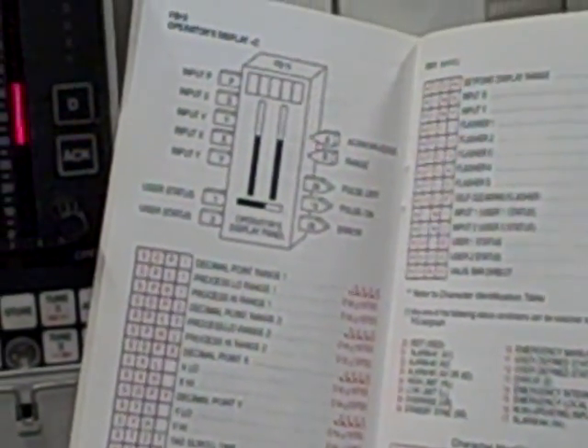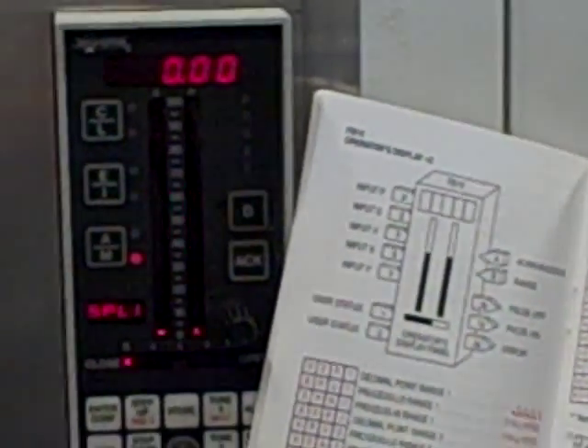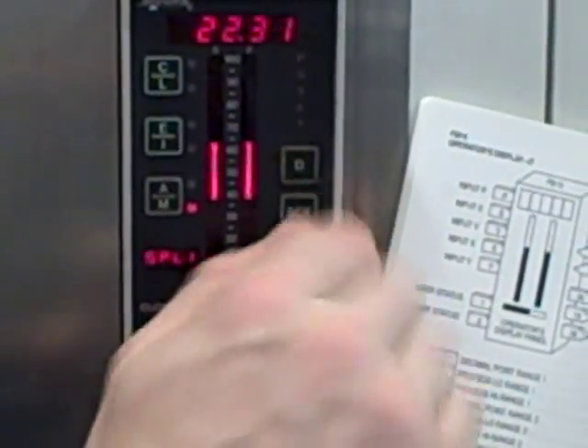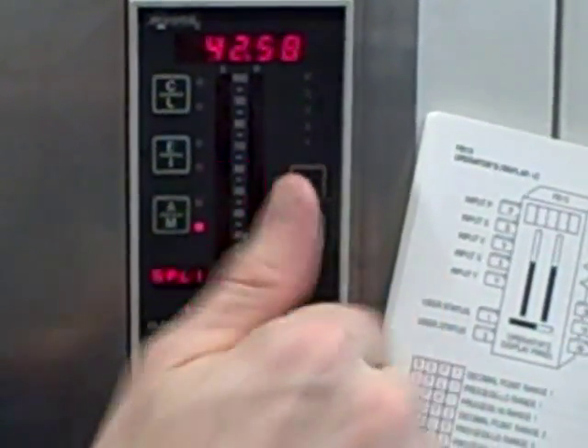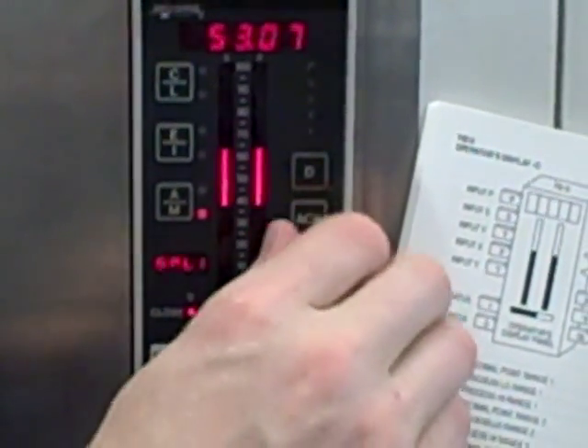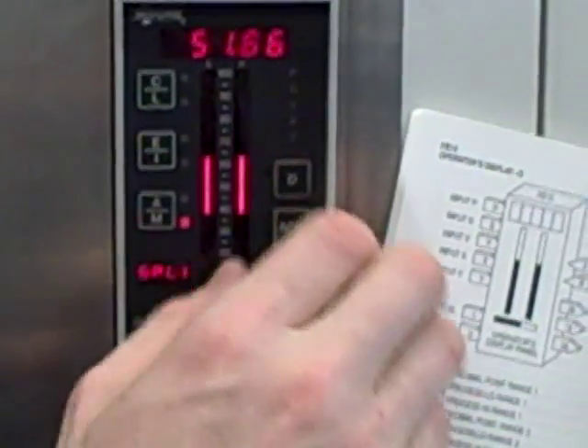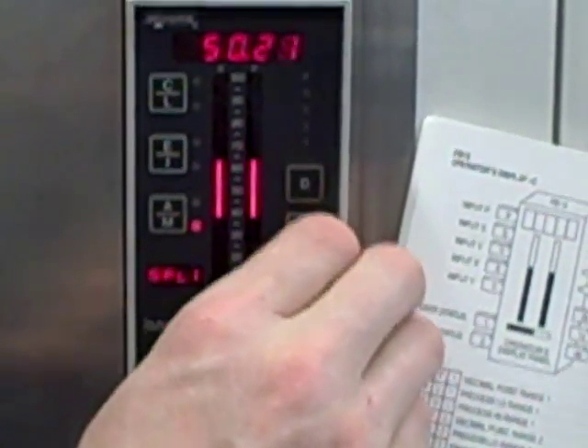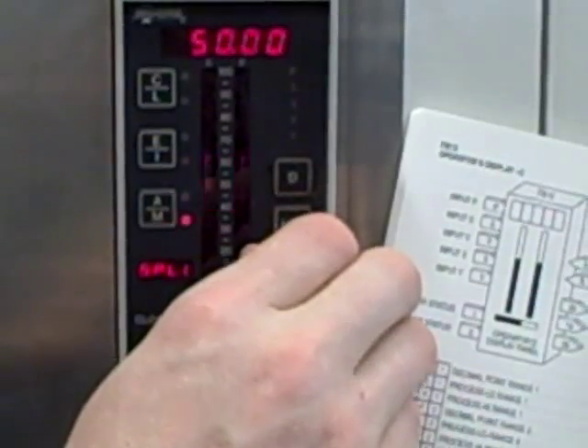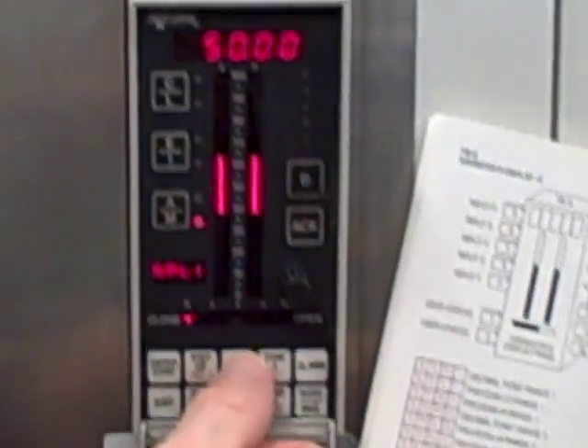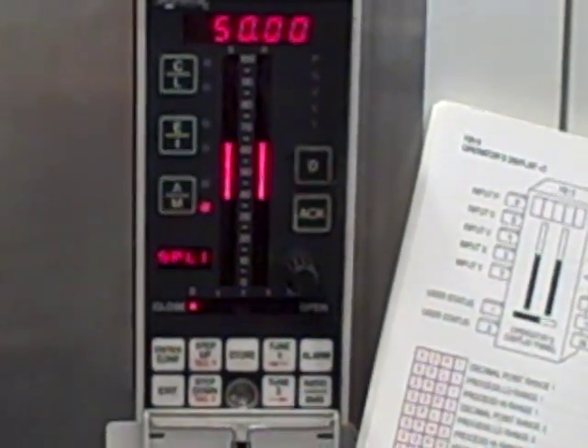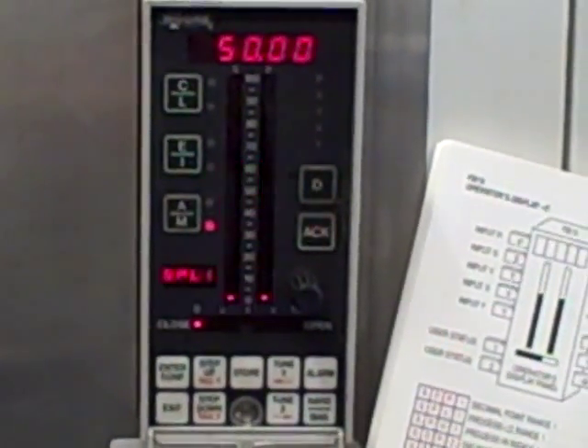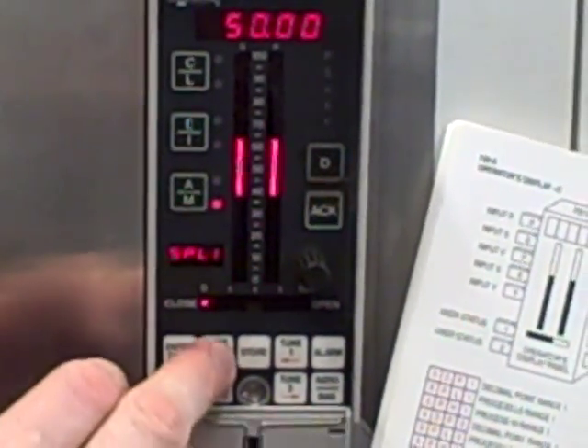The factory defaults for low and high range are 0 and 100 respectively. I don't know where your calibrated transmitter to right now. 50 and 150. 50 and 150, perfect. Okay, I'll dial this until it says 50. You'll find yourself cursing this knob. It often times jumps right over the number you're trying to get to. Usually it doesn't go that smooth. Then I hit the store button, and it blinks at me telling me it stored that parameter.